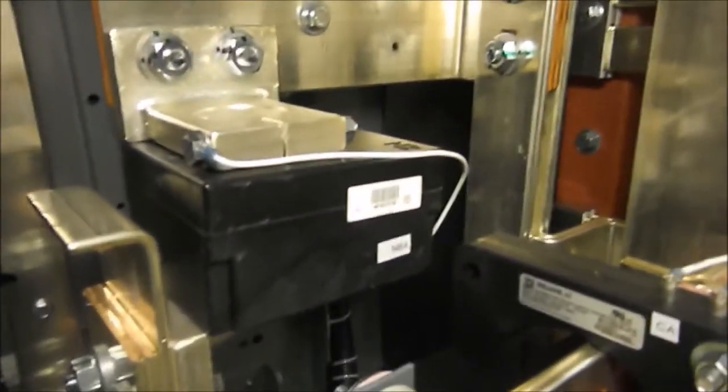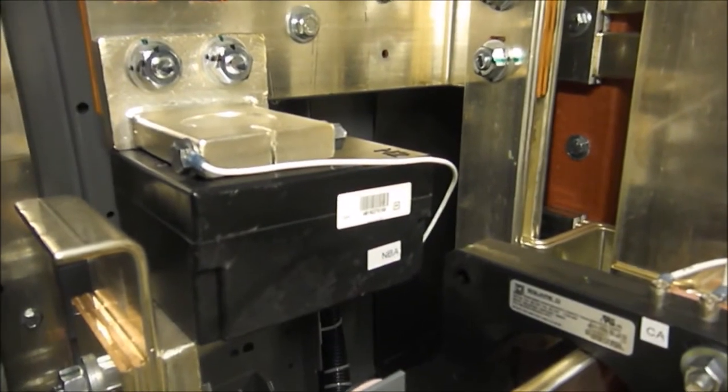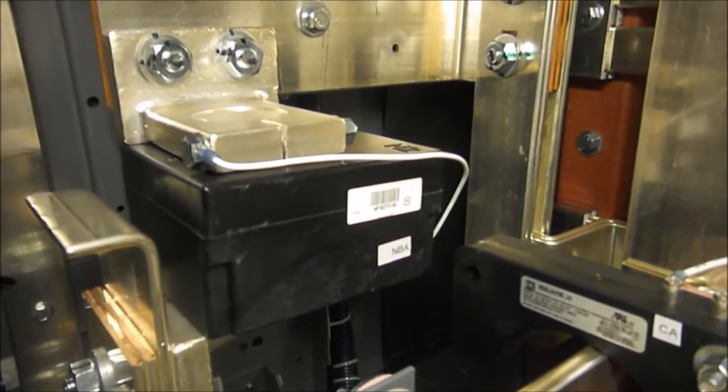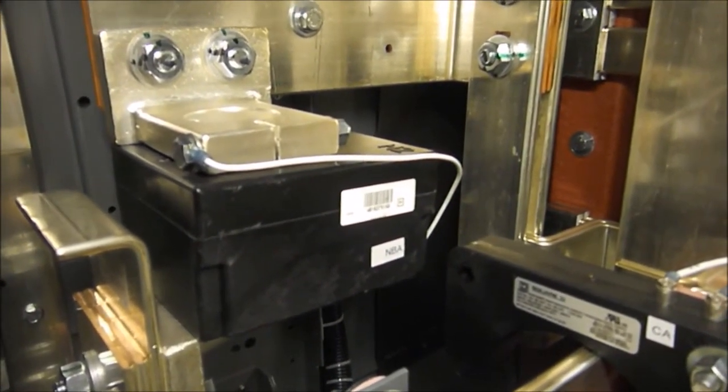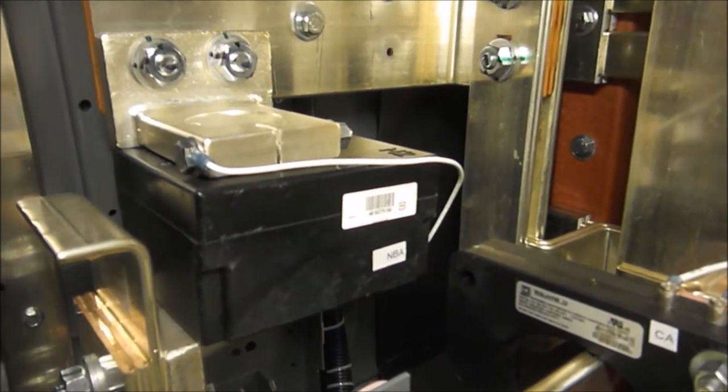On the left hand side of the switchboard we see the neutral bus contains a current transformer or neutral CT to measure neutral current through the bus and report it to the electronics of the circuit breaker.